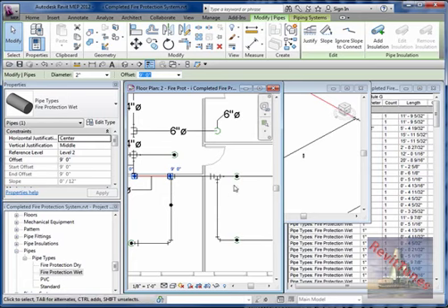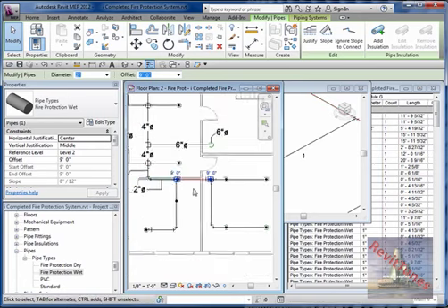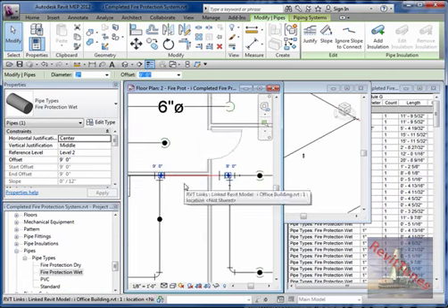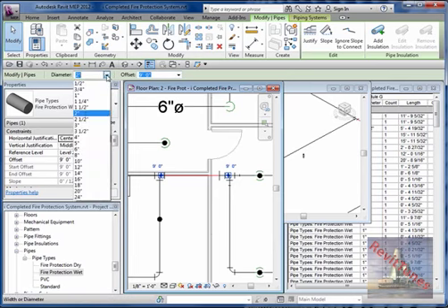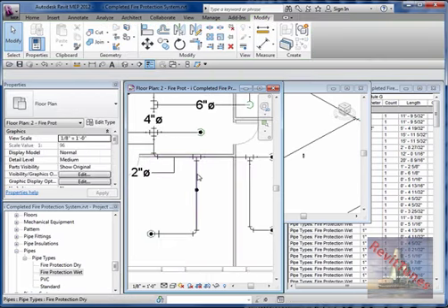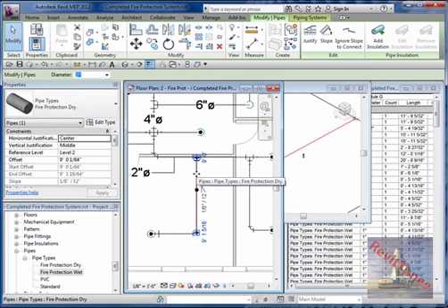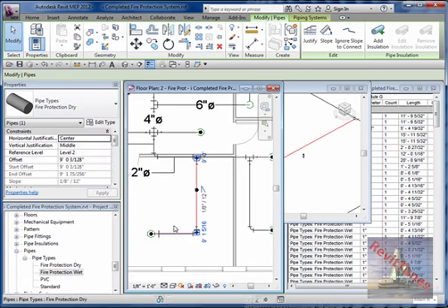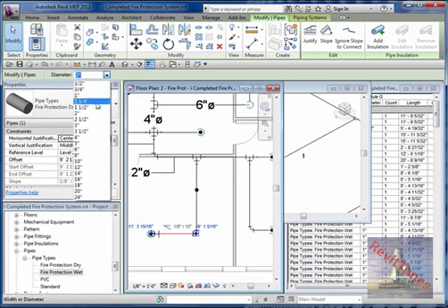And we said this was 1.5 because it was for 4 sprinklers. So this segment is the one I switched back to 2 earlier. Okay, 1.5, and for 2 we say 1.25 for 2 sprinklers. No, 1 inch for 2 sprinklers. So this should be 1 inch, and this should be 1 inch.